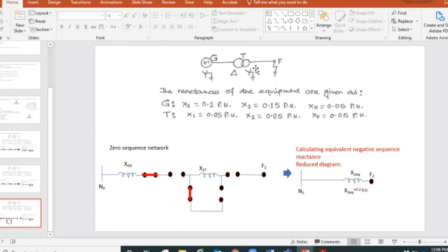So we can go to the next side, which is this side. Star connected, grounded. So the series switch should be closed. So that's the series switch. We close it and we are done with the diagram. But one thing I need to complete is that this connection needs to now go to the reference bus. So let me just label it at the top and extend it a little bit. This transformer connection needs to go to the neutral.